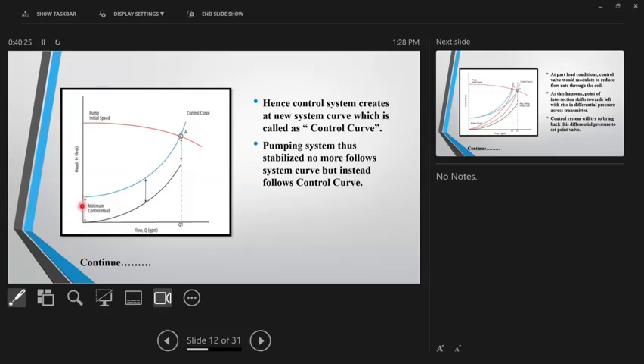This is the control head. What it means is, even if the flow is less, no problem. The control head will always be constant. So if you see this distance, this is always constant. That's how a control system devises a curve. It actually ignores your system curve. It actually creates its own curve in the algorithm and thinks that the system now has to operate like this. In this, you see all the problems are solved. There is always constant speed, constant control head, and variable speed, variable loss, of course, is a function of flow.